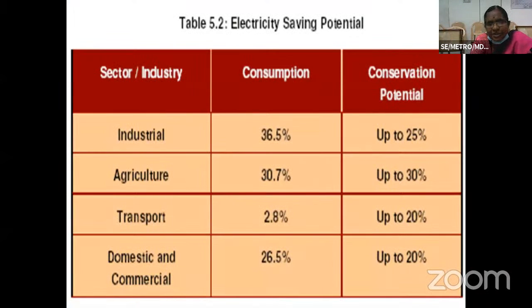So, electrical saving potential on the industrial consumption: the potential to save energy is around 25% in the industrial area, agriculture around 30%, transport around 20%, domestic and commercial sector around 20%. So in the agricultural sector, from the TANGEDCO side, we are providing more distribution transformers, reducing the length of LT line. We are now going in for the concept of LT-less network. So no LT line, so that the I squared R loss is reduced. The agricultural consumers are fed directly from the distribution transformer. And they are also provided with capacitors so that the PF is also improved, thereby the loss is also reduced.